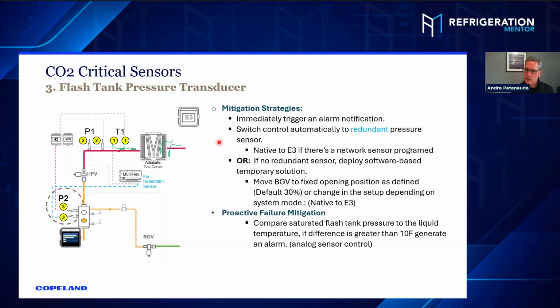If you've got a redundant sensor, you switch to the redundant sensor that's tied to the MultiFlex board. If you don't have that, then you deploy a software-based solution. You move the bypass gas to a fixed opening position. Again, in the E3, you can program it 30%, 35, 25. I mean, you can do that. Again, it's a limp-along feature that's there.